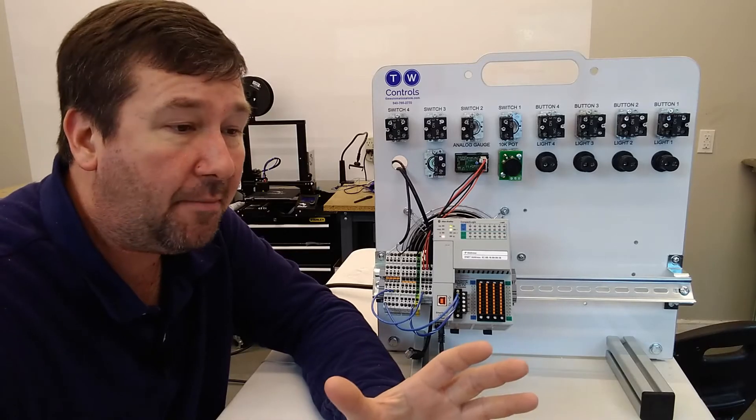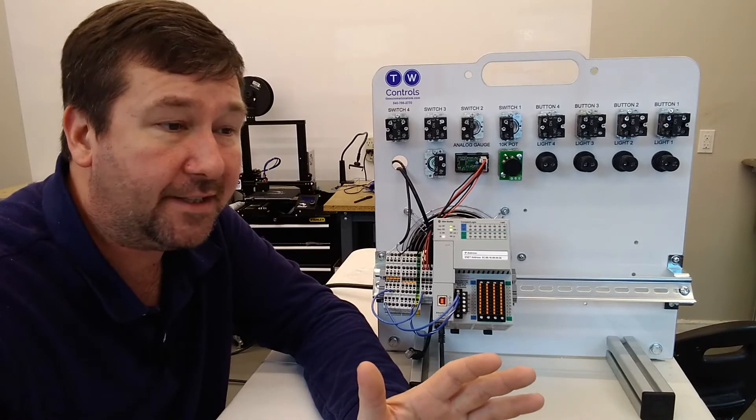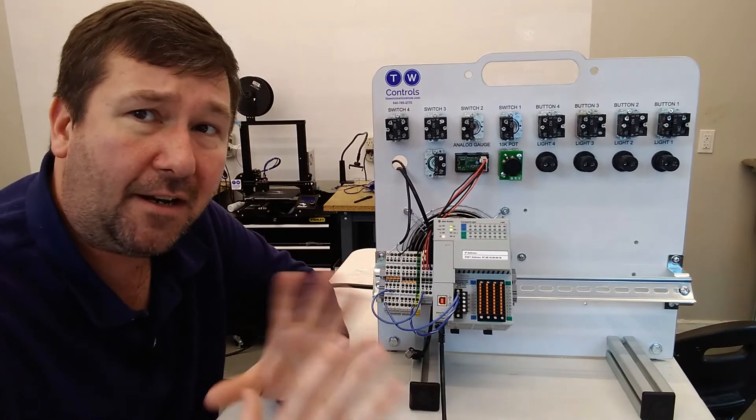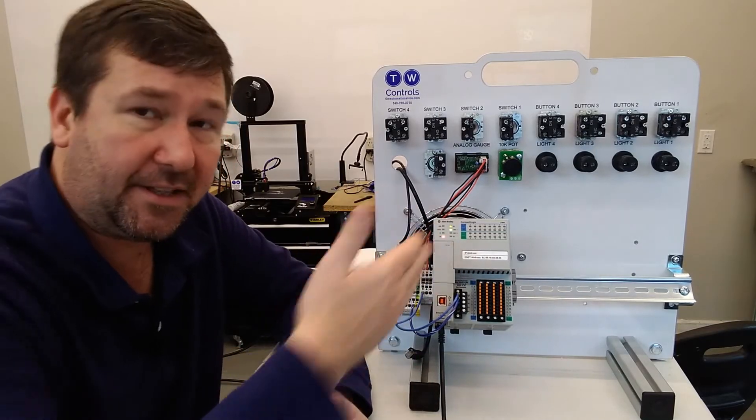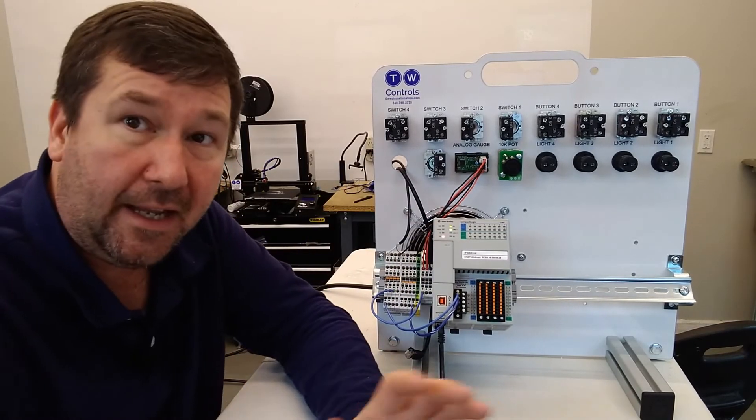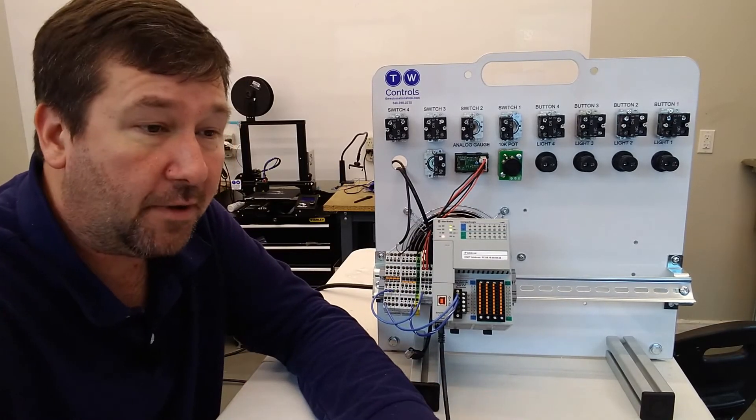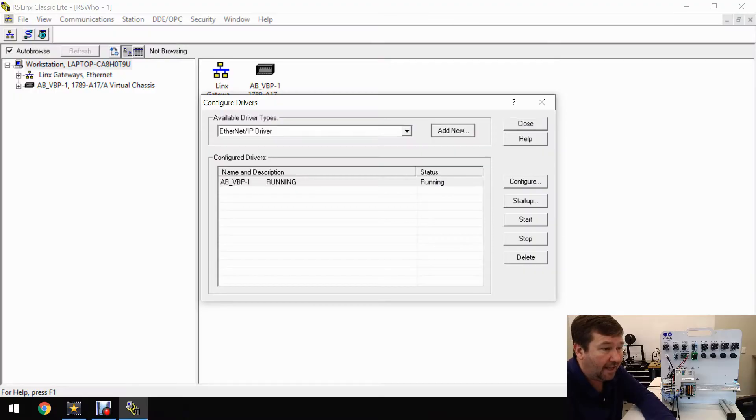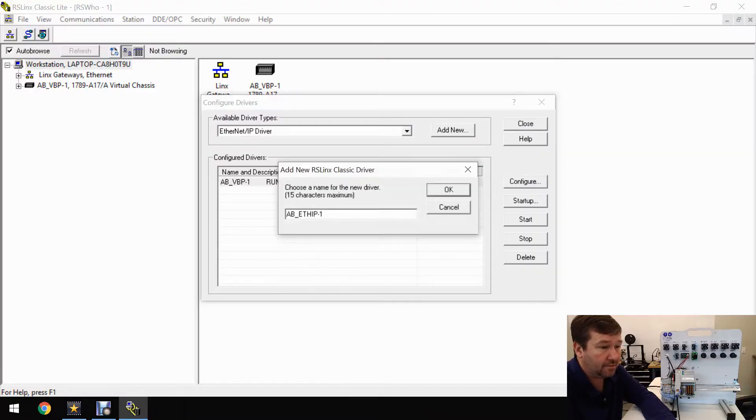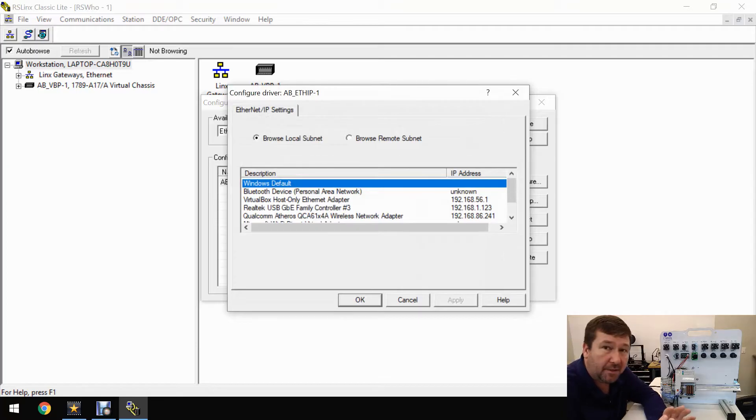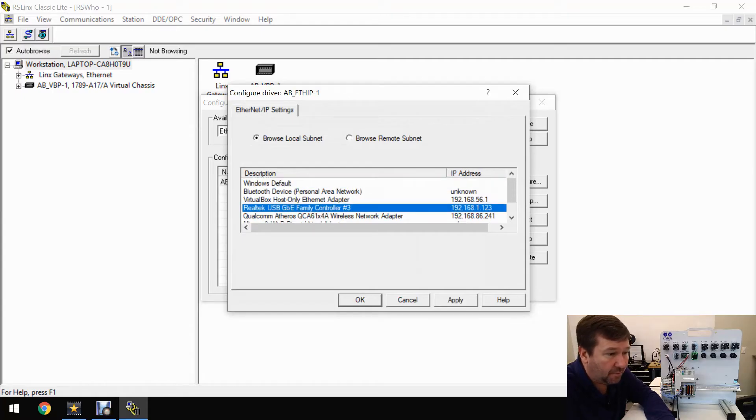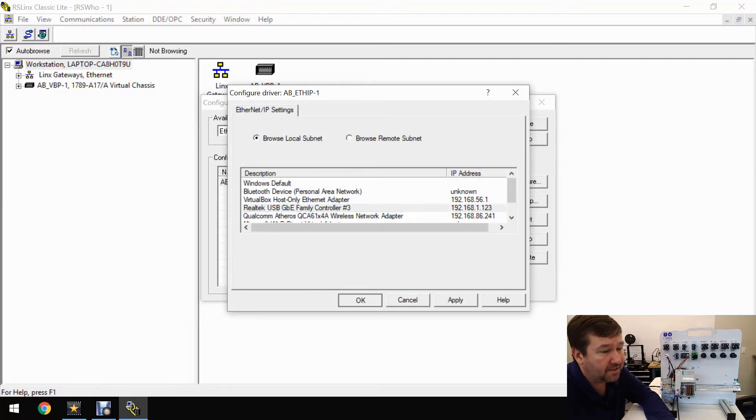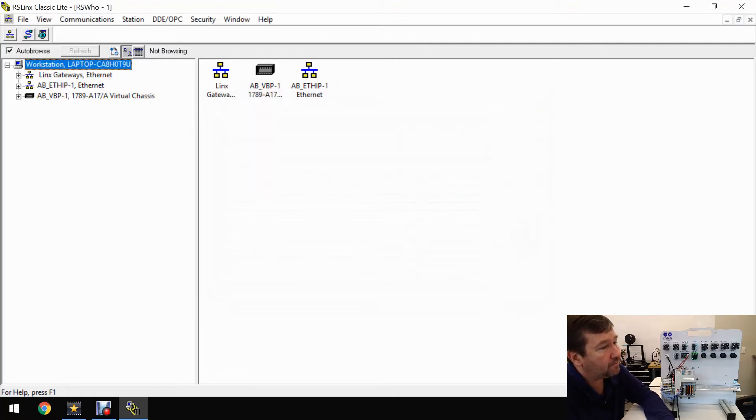What I love about the Ethernet IP driver is that if you're not on a real complicated network, like in this case we're plugged directly in, it'll do the rest of the work for you. We're going to click add new, and we'll just leave it at the default and click OK. We want to select which adapter we're going to be looking for PLCs over, and that's going to be that Realtek USB adapter in my case. We're going to select OK and close it out.